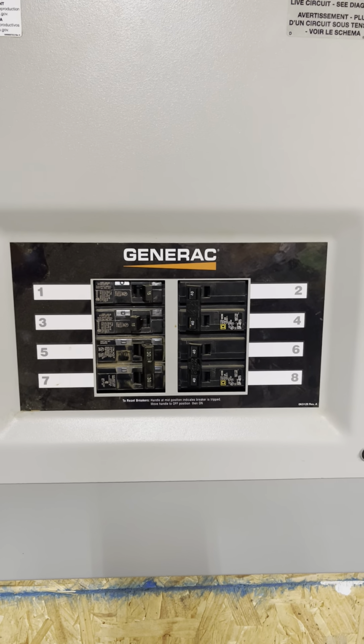So I have a 7,500 watt auto start Generac, and it has an 8 circuit panel. What I've done is put in breakers going to the 3 inverters. There's one unused breaker, and then I have a breaker that goes to a plug below the panel just in case I need just lights from the generator. And of course I've got my main grid tie panel.